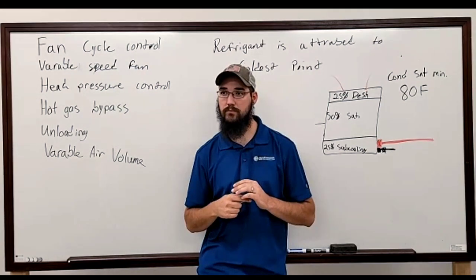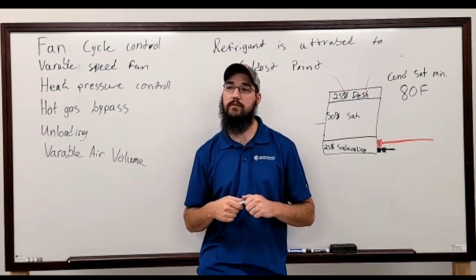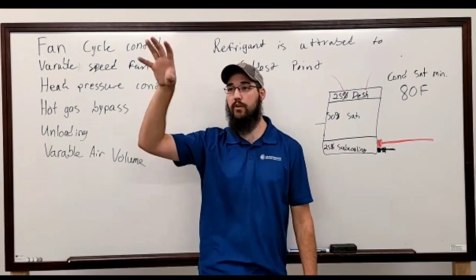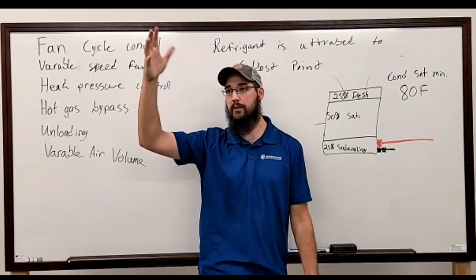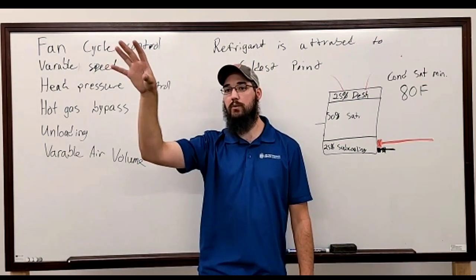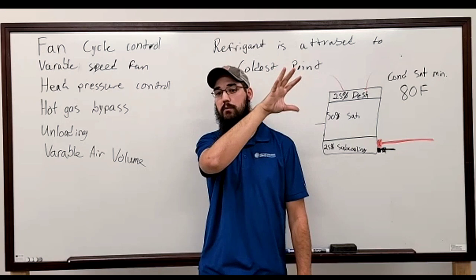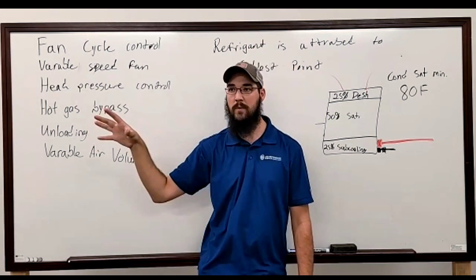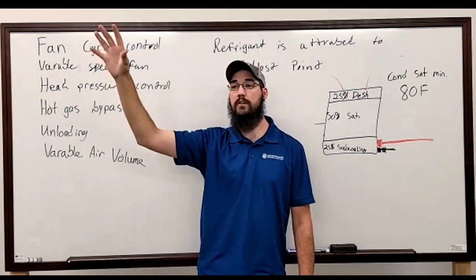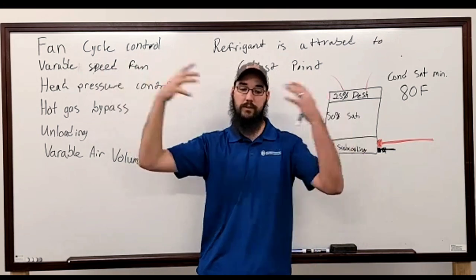So that is something done through logic software. All the control boards: you'll have a dedicated inverter board or VFD, VSD, depending on whatever brand you're working on, that runs that motor. And that VSD is reporting to the main MCB, main control board, that is monitoring the entire system and all of its readings. And that board is then communicating to the fan control board, which is then telling the fans at what levels and how to operate. And then they all just talk.